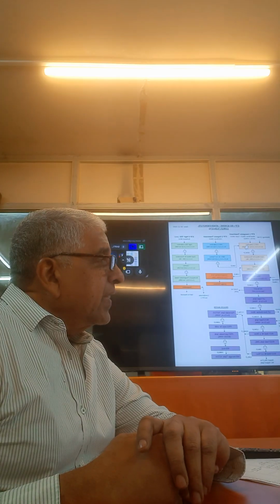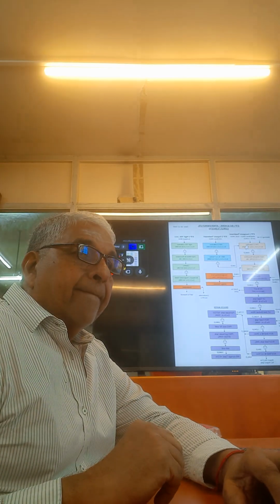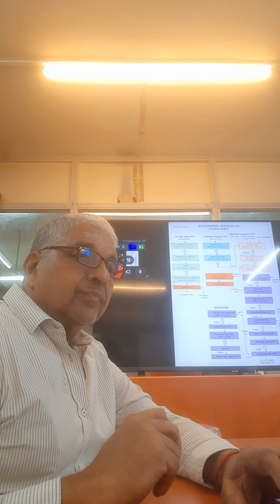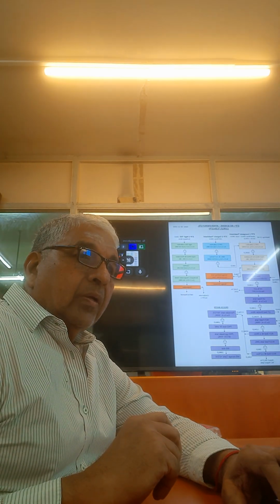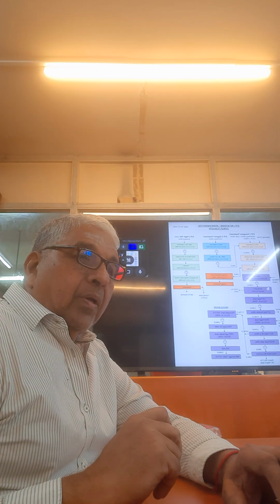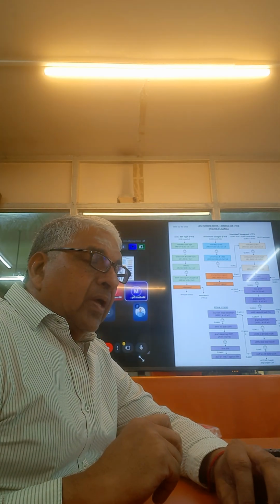Yes, correct. After the flash mixer or after the collection tank, we can add the DAF there itself. That's what I feel, because in CDs there is no oil. DAF is helpful for oil also, no? It removes oil mainly. As I said, we're moving on, it's already 20 minutes over, we'll cover the rest, but this is one issue which has to be looked into, so we'll note it down.